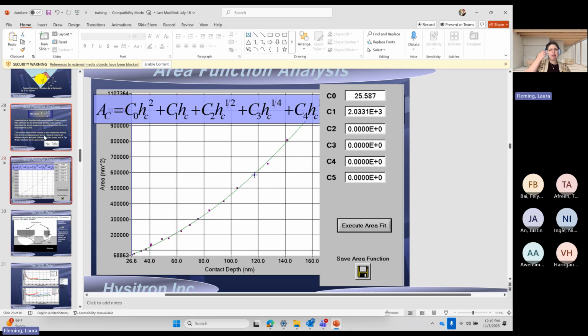So our software goes up to 6 coefficients. We typically do 3 or 4. We tie C naught for a generalized tip area function. There are some exceptions here. I have two ends of the spectrum. I have a customer who is only doing thin films and he only indents like 20 to 30 nanometers. When you're doing that kind of indentation, the tip is never going to act like an ideal Berkovich probe. It's going to be blunted. And in that case, we let C naught vary. And we only do indents in the contact depth he is interested in.